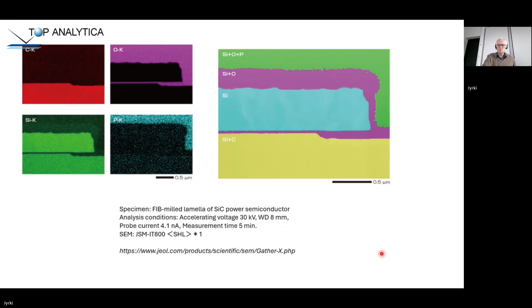If we are talking about analysis with very low X-ray energies, I mean below 1 keV, then one key factor is the detector window. The purpose of the detector window is, first of all, protecting the sensitive detector. So we have a window here, and then we have a vacuum between the detector and the window. It must be vacuum tight and mechanically strong enough to withstand the vacuum on this side, and when you are changing the samples, we have air pressure on this side. Typically for thin windows, we have a support grid made from silicon, and the typical open area is maybe 70 to 80%. That gives the mechanical strength for this window.